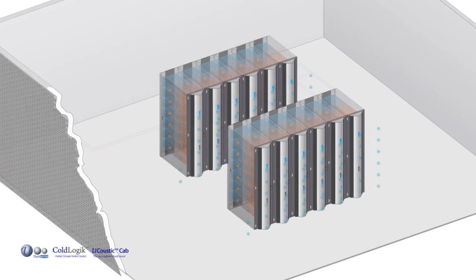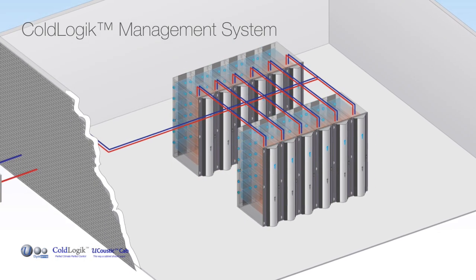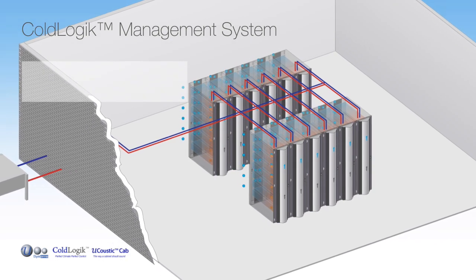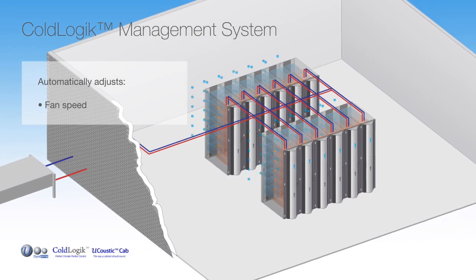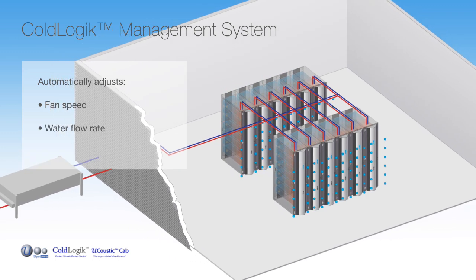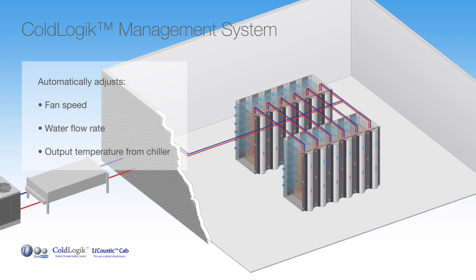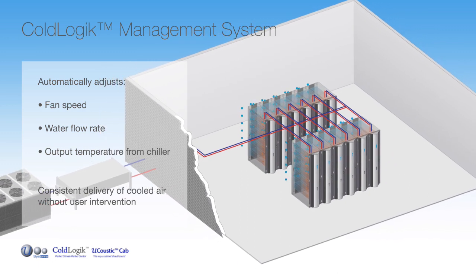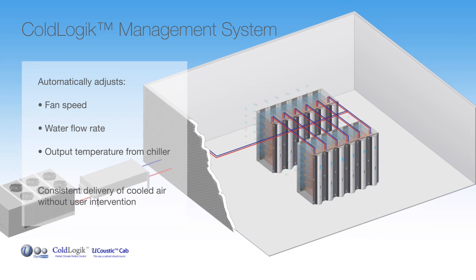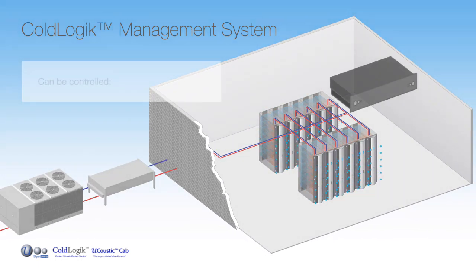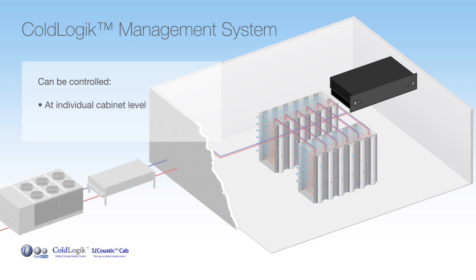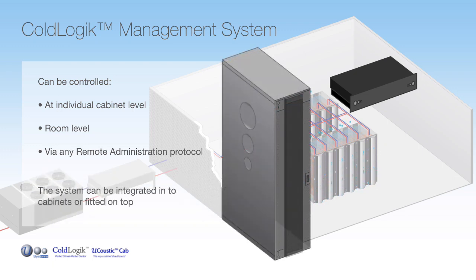The room ambient temperature is controlled by the ColdLogik management system. It achieves this by automatically adjusting the fan speed, water flow rate, and where necessary alters the output water temperature from the chiller, resulting in a consistent delivery of cooled air into the data center with no operator intervention. The whole process can also be overseen and controlled at individual cabinet level, room level, and remotely via any of the industry standard communication protocols, allowing remote administration, saving time and money. The ColdLogik management system can be fitted either internally or on top of the cabinet.